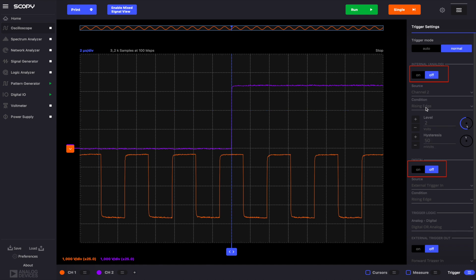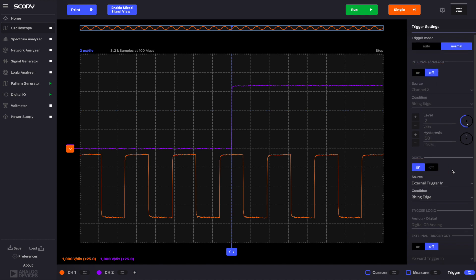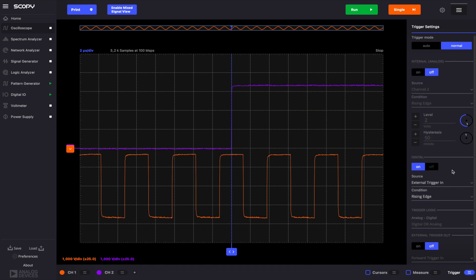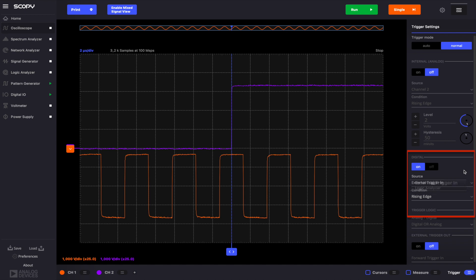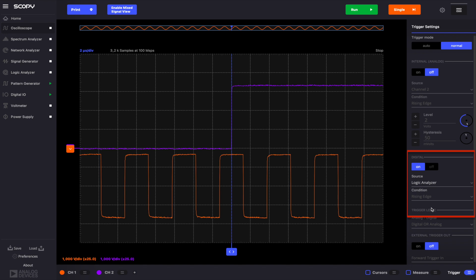Disable the internal trigger and turn on the digital one. Here, we can set the source to either the external trigger in or the logic analyzer. When we were discussing the logic analyzer trigger options, an example using the external trigger in was shown. Since the procedure is the same for the oscilloscope, now we'll demonstrate how to do cross-instrument triggering. That is, to trigger data capture for the oscilloscope when the logic analyzer's condition is fulfilled, and vice versa.